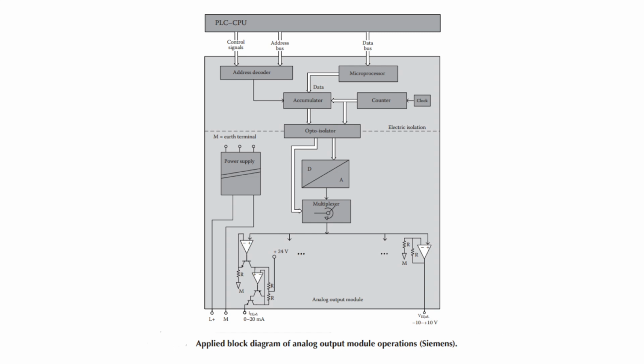The analog output signals are always DC in nature, but they can also control AC devices. For example, an AC motor controller like a soft starter can be driven by a varying DC signal from the analog output module. So by applying a varying DC output voltage, for example in a 0 to 10 volt range, to the AC controller's input, the AC motor speed can be adjusted.